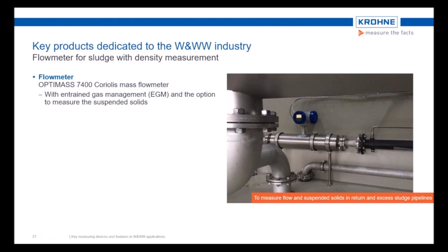The OPTIMASS 7400 Coriolis mass flow meter is an excellent measuring device for measuring sludge such as return or excess sludge. Comparing this device with a conventional mag meter, the operator can make use of the additional feature to also display and output the density of the measured media. This is easily realized with an offset calibration with the local conditions and the real values, which might be different within the different plants due to the different sludge conditions.